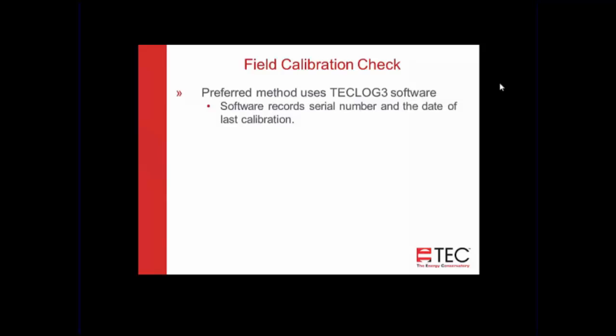So you're documenting that for sure the gauge that you're comparing them against has been recently calibrated. It's been calibrated within the last 6 months, and you've got documentation of that. And also, you can't mistype or miswrite the serial number of the other gauges that you're doing the comparison against, because that information is all brought in directly from the chip on the gauges.